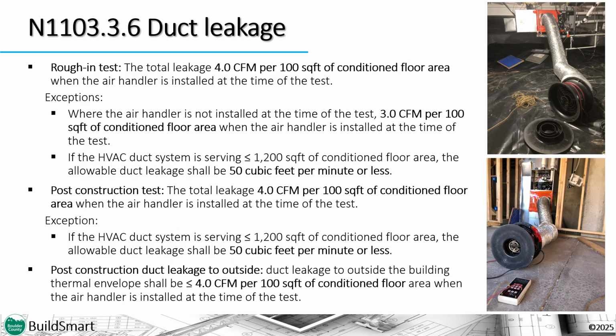The compliance metric that is used to demonstrate compliance with the BuildSmart code depends on when the system is tested and if the system is servicing more than 1,200 square feet. If you test at a rough stage of construction, the system can't leak more than 4 CFM per 100 square feet of conditioned floor area served by the system itself. For a 2,000 square foot home, for example, the system can't leak more than 80 CFM of air.